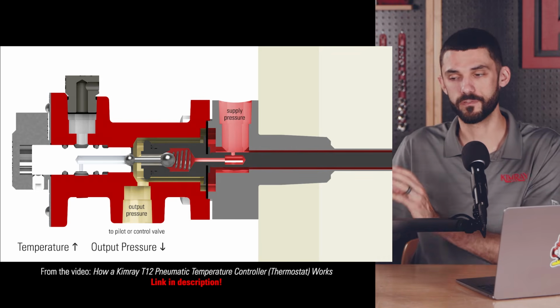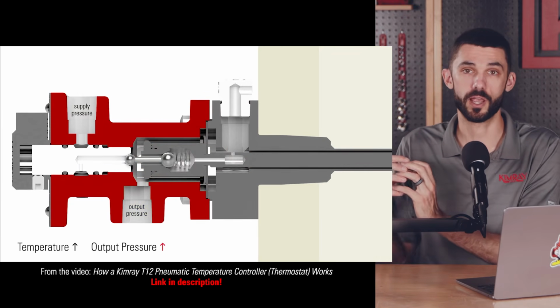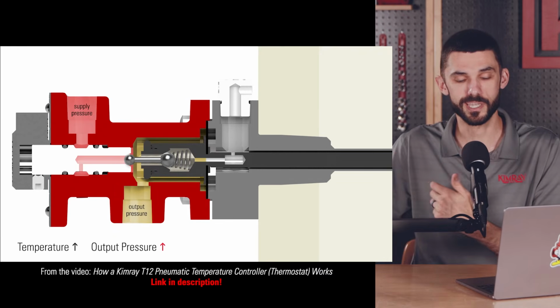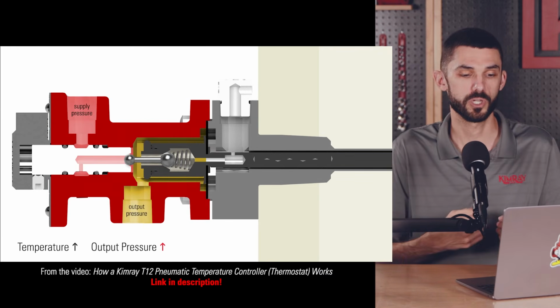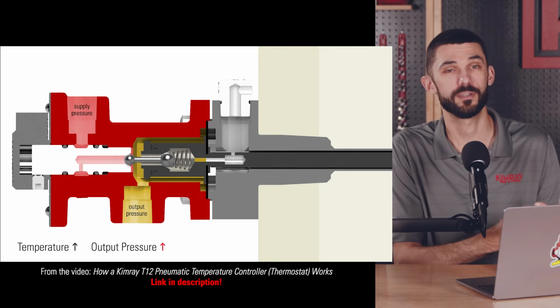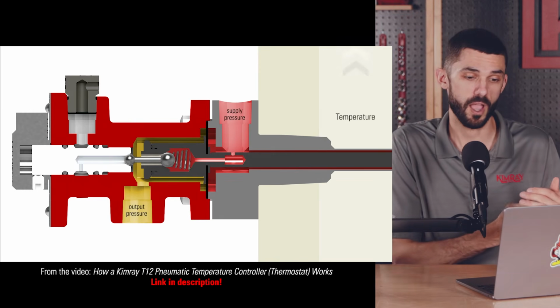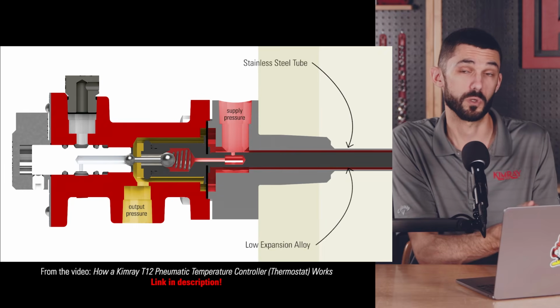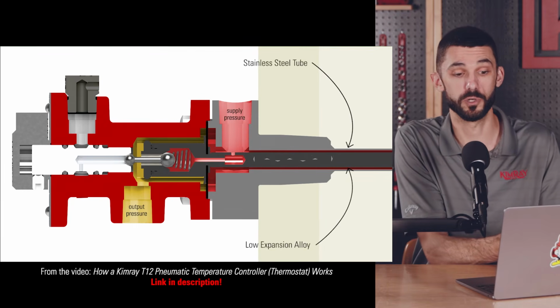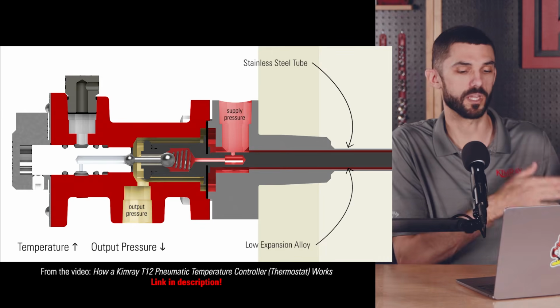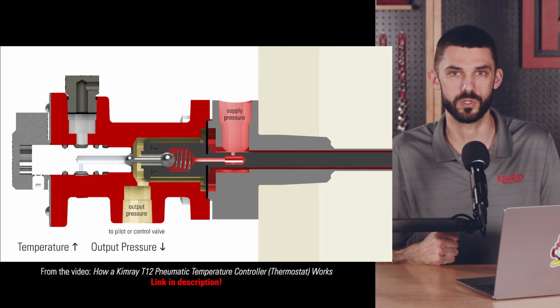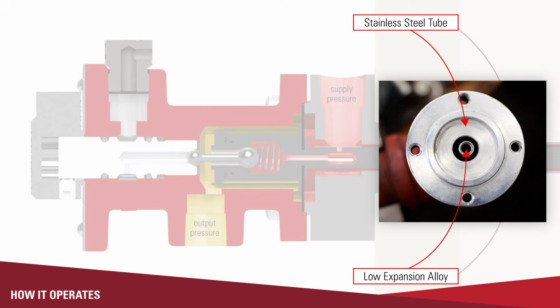Now, when things cool off, you'll have a contraction of the sensing element, which would then push the low expansion alloy rod and the diaphragm assembly further out away from the vessel, which would cause supply to go to output, opening up your burner valve to then increase temperature. It's important that the low expansion alloy rod does not come into contact with the outer shell. And that's something that I'll move into talking about troubleshooting.